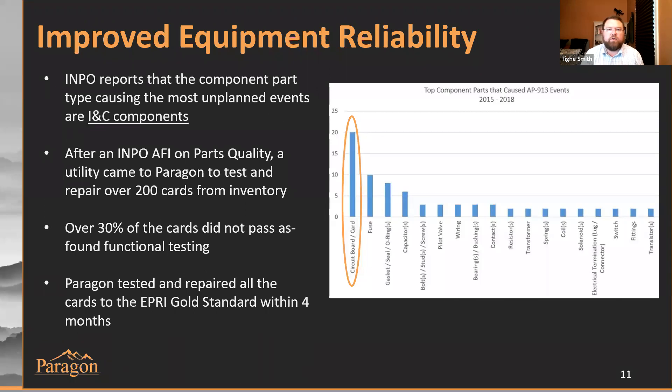Another benefit of I&C repair is that it improves equipment reliability. When you look at the INPO research on parts that cause AP 913 related events, circuit cards and circuit boards are the number one reason for plant-related maintenance events. When you're pulling parts out of your warehouse, they may not have been functionally tested for a very long time. A recent utility had an AFI on parts quality related to events caused by circuit cards and I&C components coming out of inventory from their warehouse. They sent 200 cards to Paragon for testing and repair, and upon as-found testing, about 30% of those cards either weren't working at all or failed to meet functional test requirements.